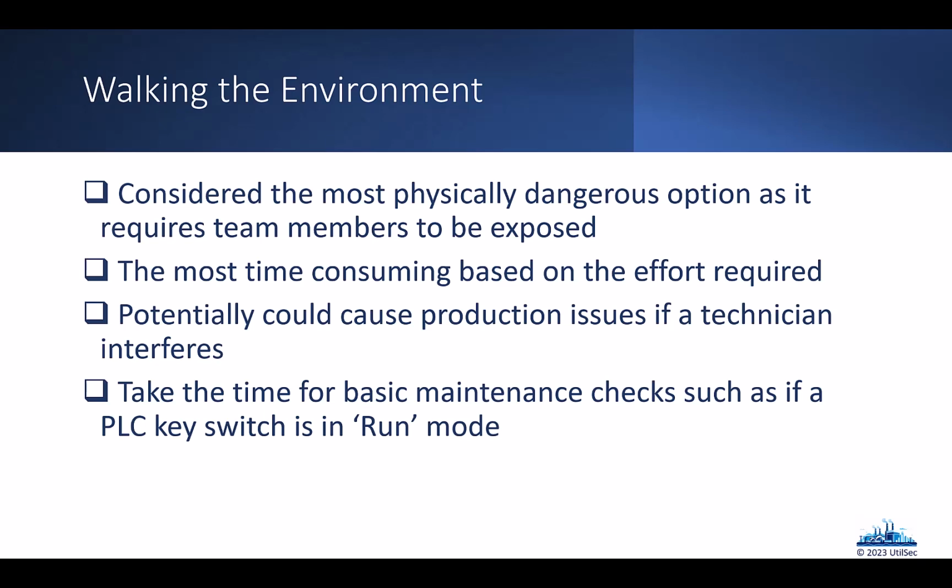Remember, run mode means that the PLC is operating, it's running, it's doing its job, and that it can't be remotely updated. That means an attacker can't come back and upload different code to it. They can't upload new firmware, and they can't update the program that's running on the PLC. So we want to make sure all of those PLCs are in run mode.